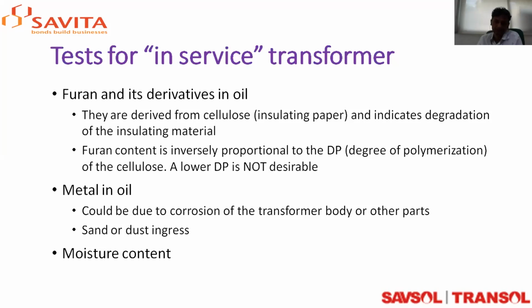Now where does furan come from? If you take fresh oil, you will not find furans. Basically, furan is a chemical or molecule formed from the degradation of paper, specifically degradation of cellulose in the presence of moisture and temperature.